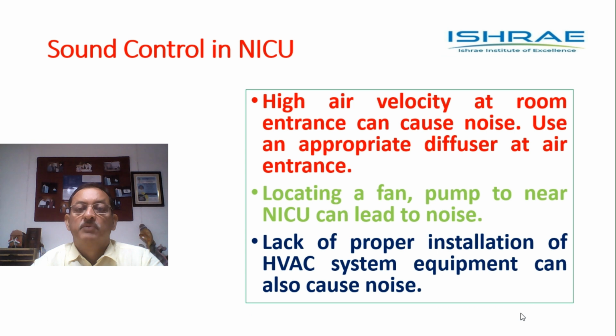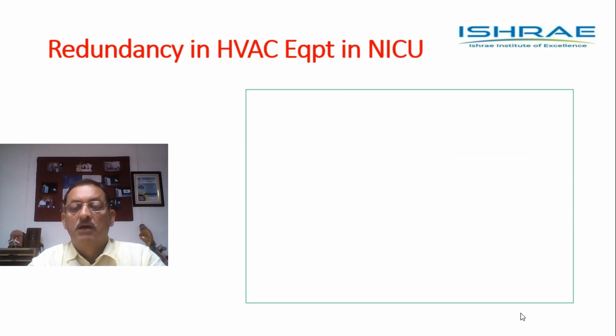Sound control is the next requirement. High air velocity at the room entrance can cause noise. Use of an appropriate diffuser at the air entrance is suggested so that when the air finally comes into the NICU, the velocity of air is less and so noise is not created. If a fan or a pump or any AHU is located too near the NICU, that can also lead to noise. Lack of proper installation of HVAC system or equipment can also cause noise, so we have to be careful about it. This noise will not let the infant sleep, and that will cause harm to their health.